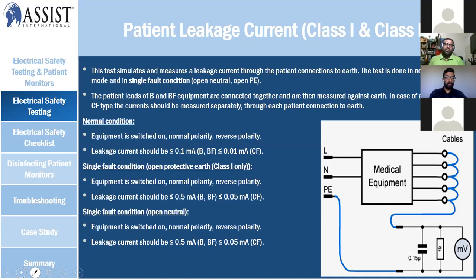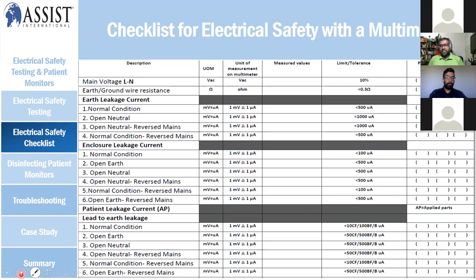You have to be careful — there is quite a lot of risk, such as when opening the neutral line and making connections. If done incorrectly, you can get electrocuted. But you can still measure leakage current this way. Looking at the checklist, using one millivolt equal to one microamp, you are limited to measuring main voltage, earth resistance, earth leakage current, enclosure leakage, patient leakage current, and lead-to-earth leakage current. These measurements are good enough to assess leakage current on your equipment.